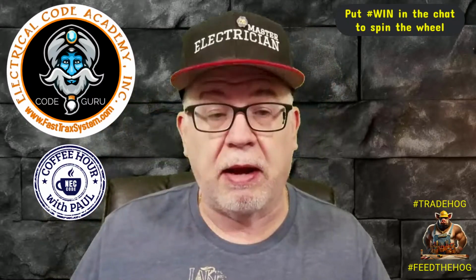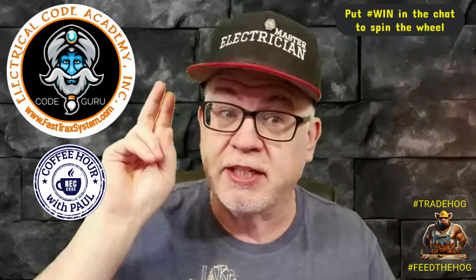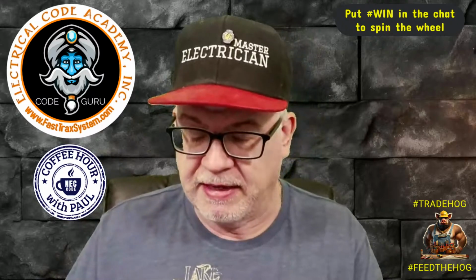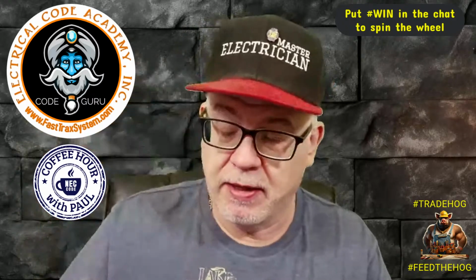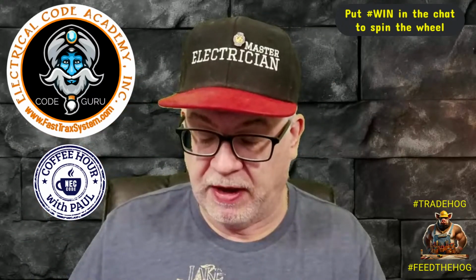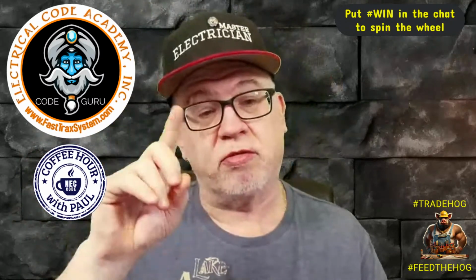And you say, well, how do I know that? Well, what if I had 24 amps of continuous load? Then I take that 24, multiply it by 1.25, and miraculously that equals 30, right? So it is the reciprocal.